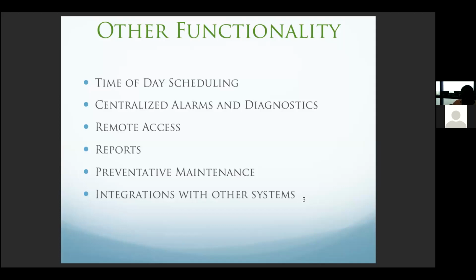Integrations with other systems is quite interesting as well. As we discussed, back in the day there may have been proprietary protocols used by all companies. And today, now that we've moved towards BACnet, there are still a lot of buildings out there that are older and still have legacy systems that are from 50 years ago, if anything, sometimes. So in that scenario, what we do is we try to see if there may be a converter or gateway, whatever you want to call it, that would convert their proprietary communication into BACnet. And if it is capable of doing that, then we just connect to that gateway because that's already BACnet, and then we bring it onto our system.